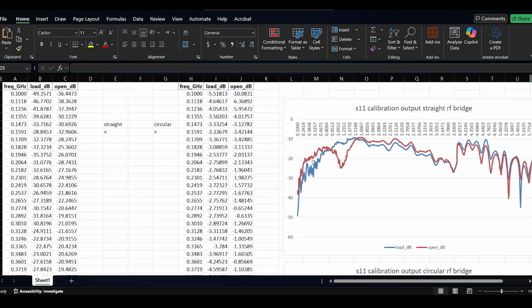To some degree, we can use this region and this region, and definitely not the crossing points, because at the crossing point we cannot differentiate between the open and load. Therefore, especially at these crossing frequencies, we cannot use this RF bridge. At much higher frequencies, above 3 or 4 gigahertz, you can also see very bad behavior from the RF bridge.